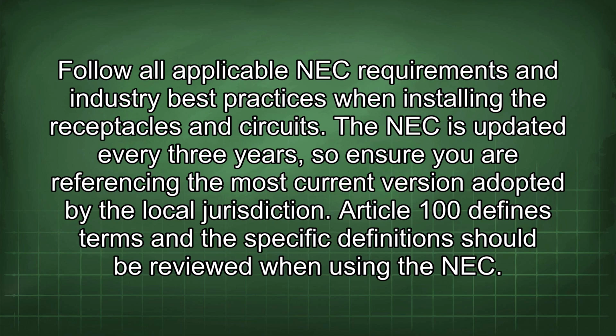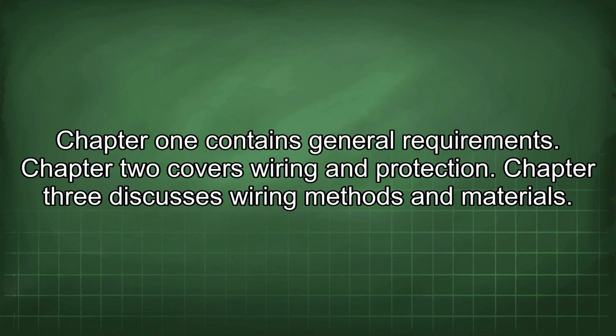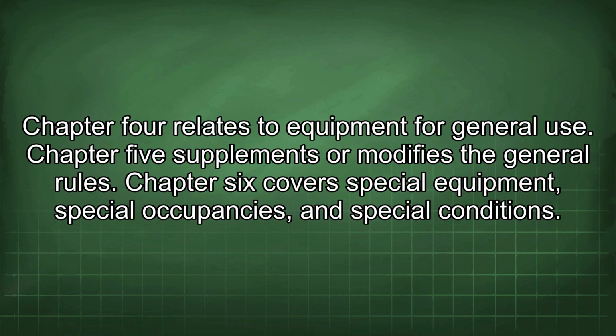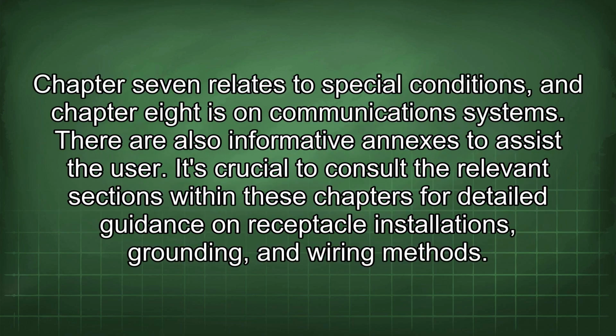The NEC is updated every 3 years, so ensure you are referencing the most current version adopted by the local jurisdiction. Article 100 defines terms, and the specific definition should be reviewed when using the NEC. Chapter 1 contains general requirements. Chapter 2 covers wiring and protection. Chapter 3 discusses wiring methods and materials. Chapter 4 relates to equipment for general use. Chapter 5 supplements or modifies the general rules. Chapter 6 covers special equipment, special occupancies, and special conditions. Chapter 7 relates to special conditions, and Chapter 8 is on communication systems.